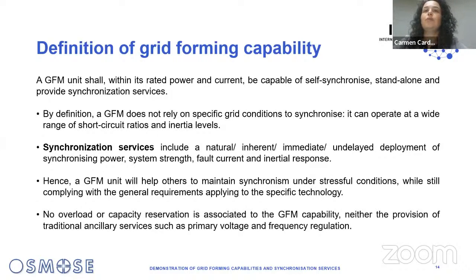So to put it in more comprehensible words, what this means is that by definition, a grid forming unit does not rely on specific conditions to synchronize. So it can operate on a wide range of short circuit ratios and inertia levels, which are the challenges that a grid following unit is facing today. Then we have this definition of synchronization services, which actually includes a notion of natural, inherent, immediate, or undelayed deployment of synchronizing power, system strength, fault current, and inertial response. Again, this is the main specificity of a grid forming unit and what a grid following unit cannot perform.